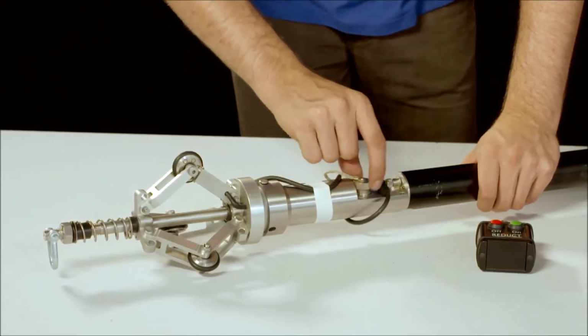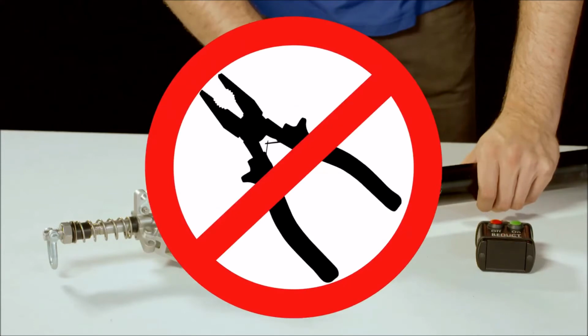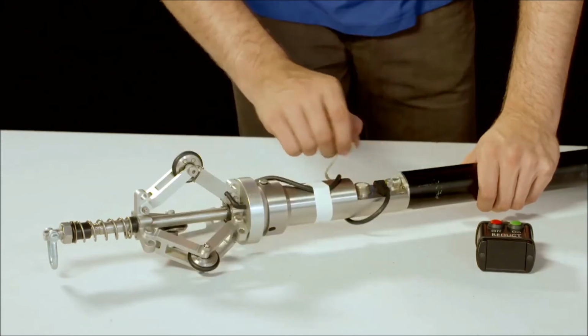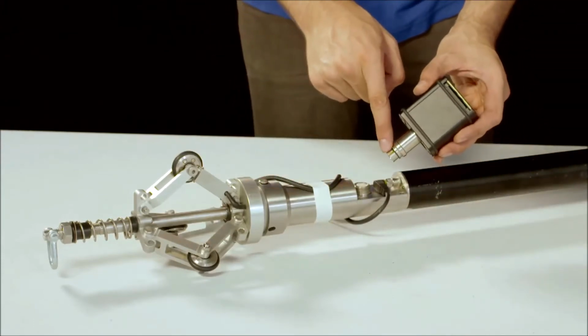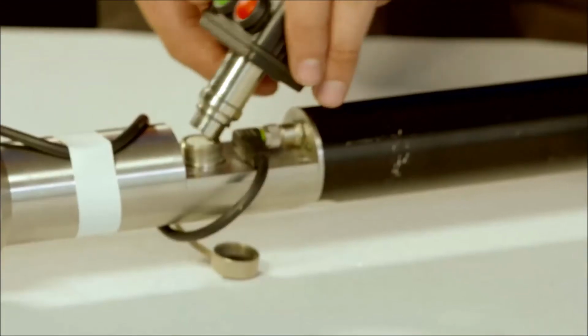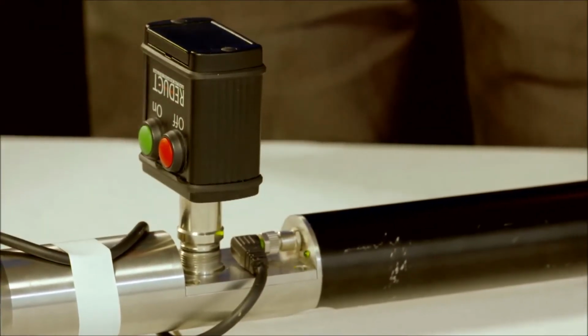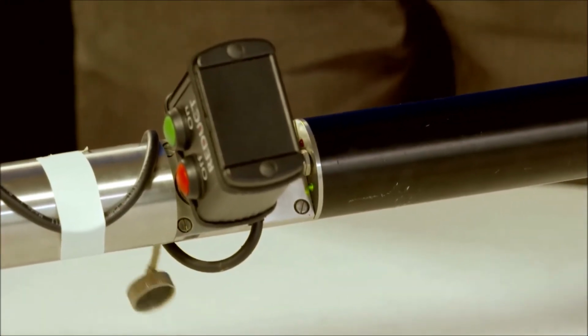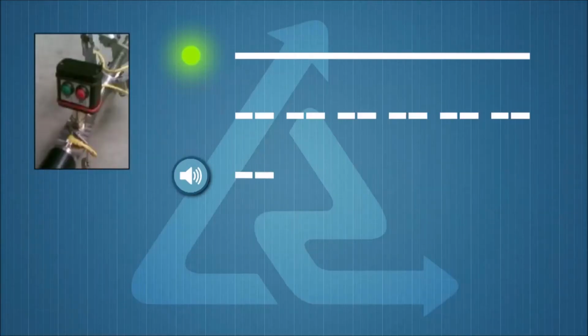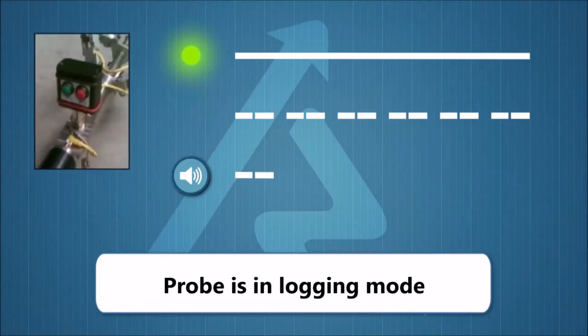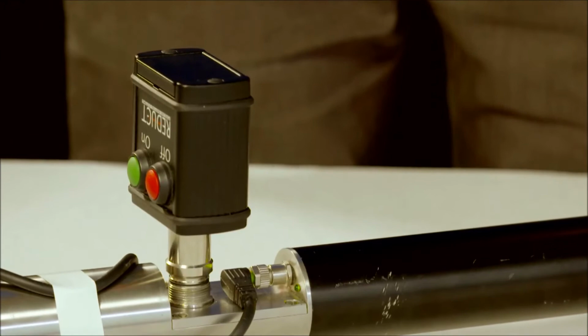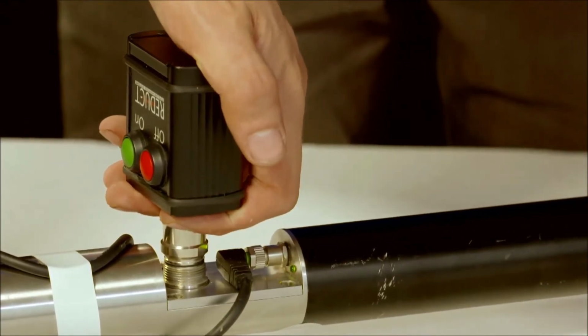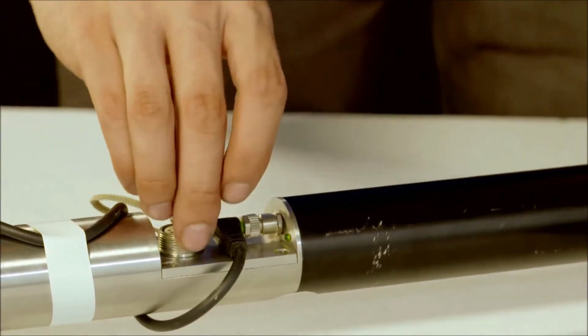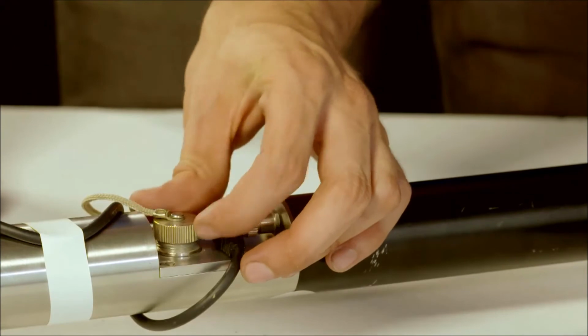To switch the probe on, remove the protective cap manually, insert the control unit, and press the on button. If, after switching the probe on, you hear two beeps, the green LED is on continuously, and the red LED flashes twice intermittently, the probe is in logging mode and ready to map. Remove the control unit. Close the protective cap, and proceed to the pipe.